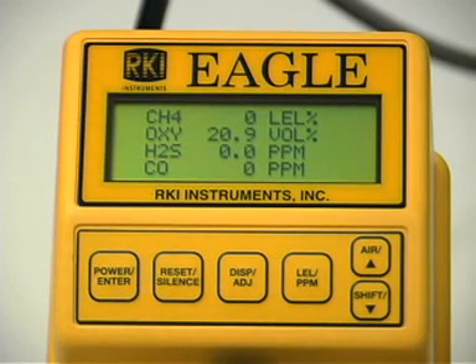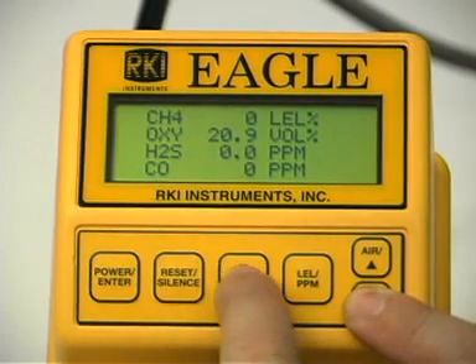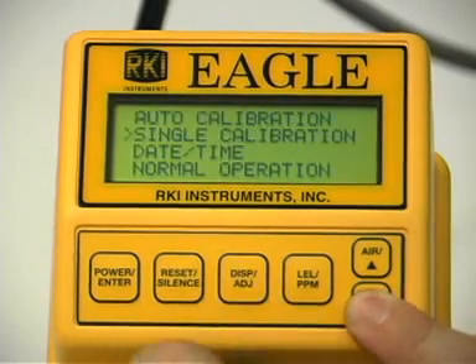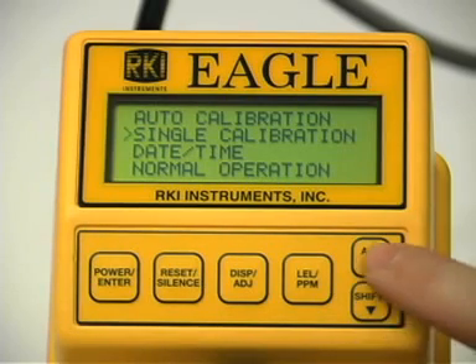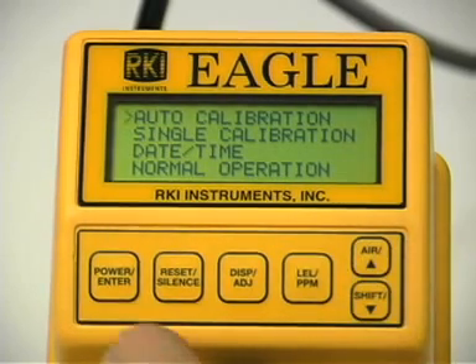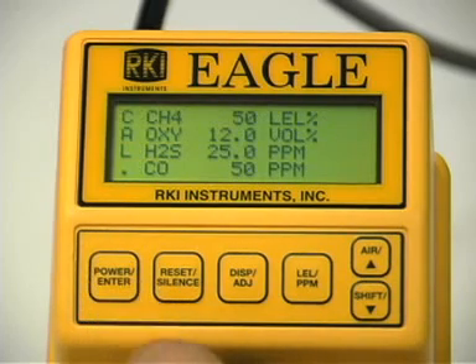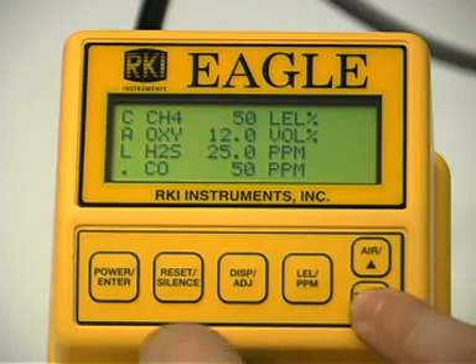If one or more concentrations displayed in the calibration values screen does not match the concentrations listed on your calibration cylinder, you need to adjust the auto calibration values. From normal operation mode, press and hold the Shift Down button, then simultaneously press the Display Adjust button. Select the auto calibration screen and press the Power Enter button. To adjust the auto calibration values, press and hold the Down button, then simultaneously press the Display Adjust button.